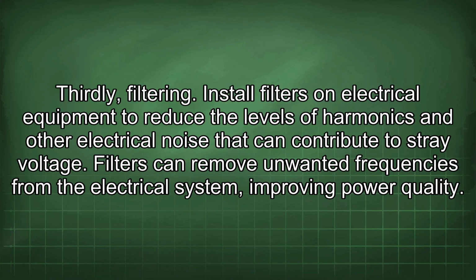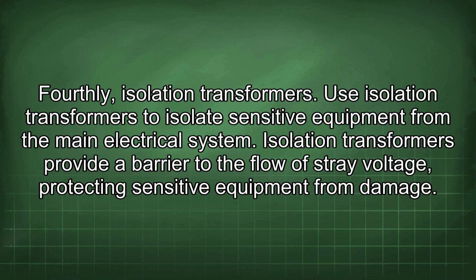Thirdly, filtering. Install filters on electrical equipment to reduce the levels of harmonics and other electrical noise that can contribute to stray voltage. Filters can remove unwanted frequencies from the electrical system, improving power quality. Fourthly, isolation transformers. Use isolation transformers to isolate sensitive equipment from the main electrical system. Isolation transformers provide a barrier to the flow of stray voltage, protecting sensitive equipment from damage.